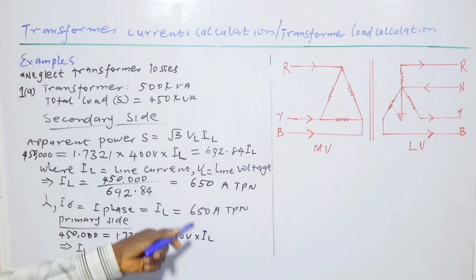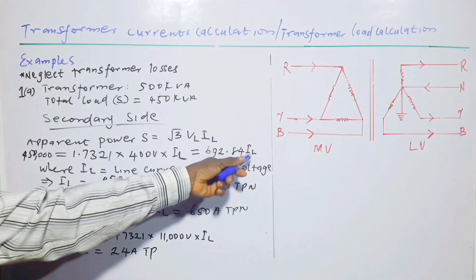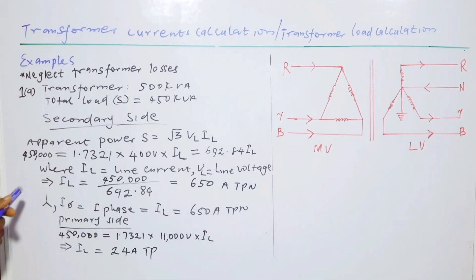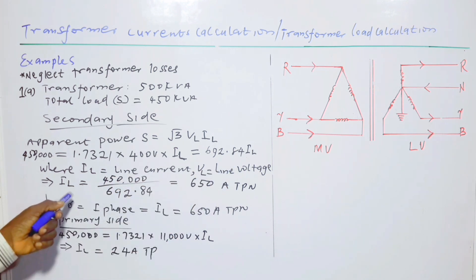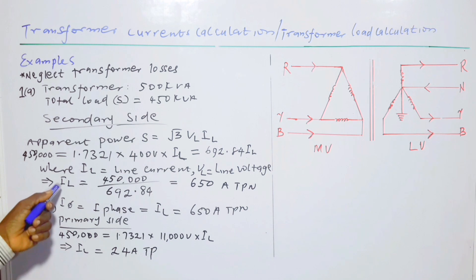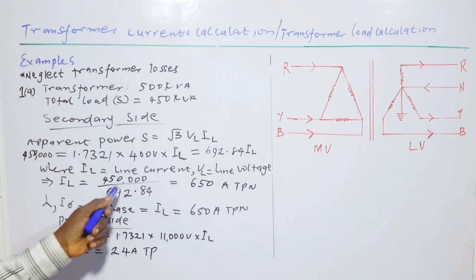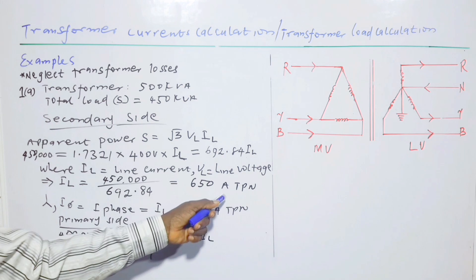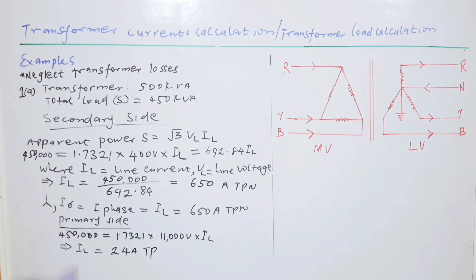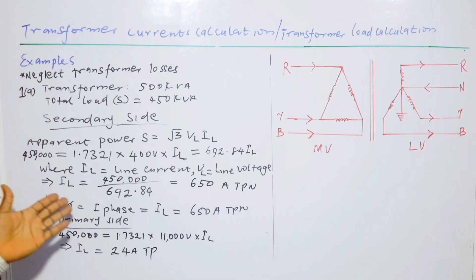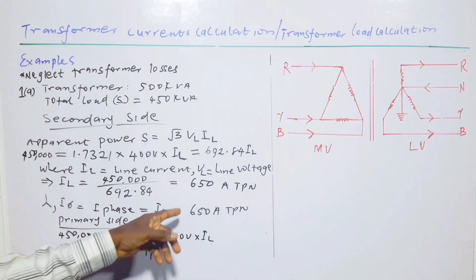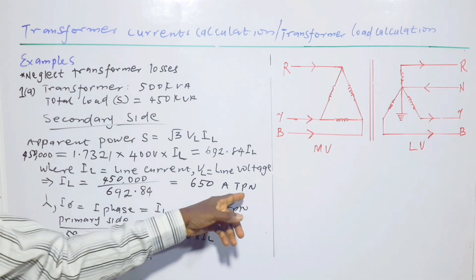From that formula, 450,000 = √3 × 400 × I_L, giving I_L = 650 amperes. So the line current, which equals the phase current, is 650 A, three-phase with neutral.